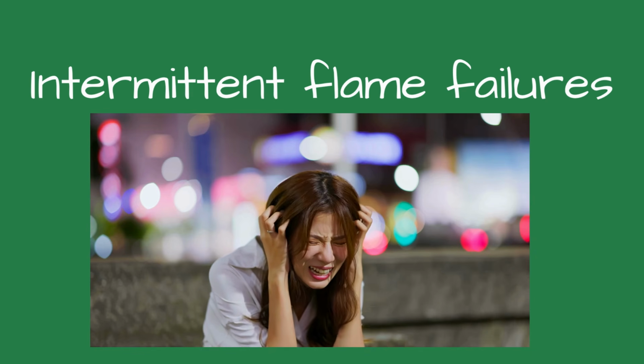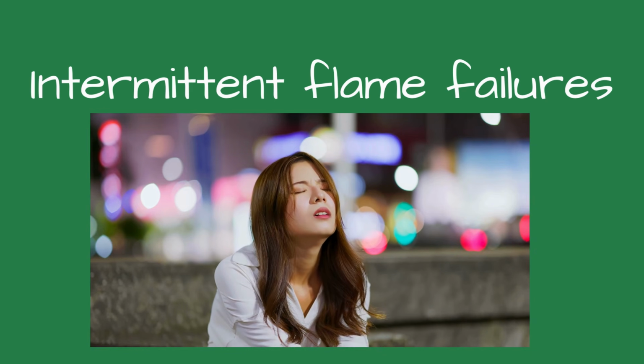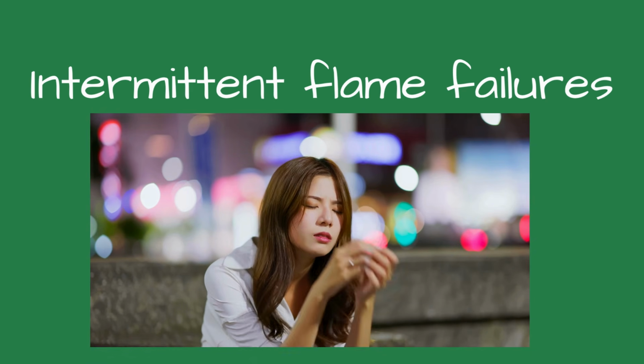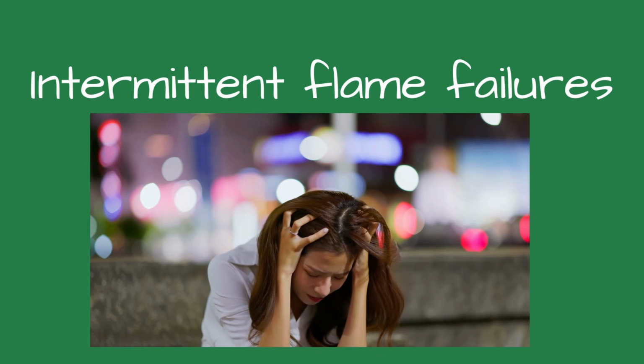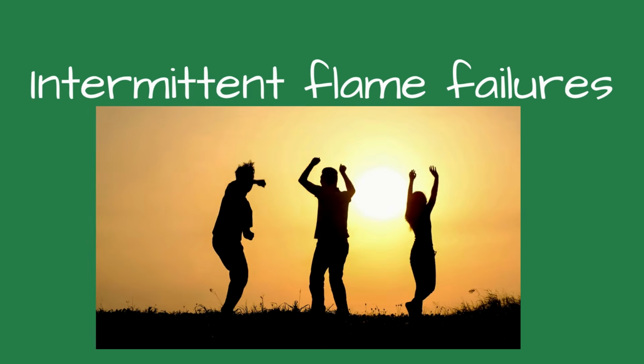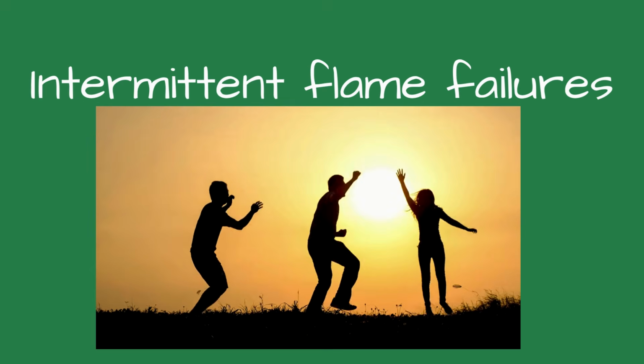Intermittent flame failures can and do test your patience, but not your skill. By following the firing sequence, checking connections, and using flame signal data as your compass, you'll solve even the trickiest cases.